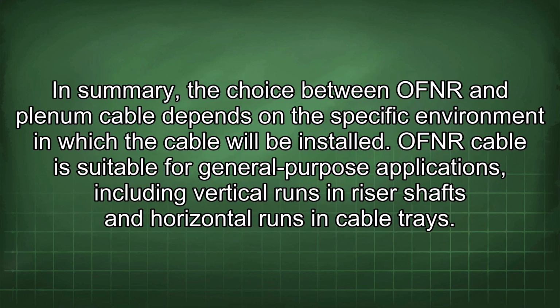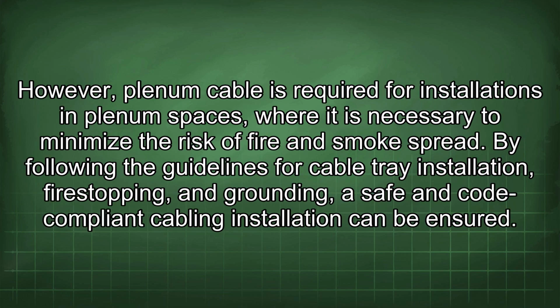In summary, the choice between OFNR and plenum cable depends on the specific environment in which the cable will be installed. OFNR cable is suitable for general-purpose applications, including vertical runs in riser shafts and horizontal runs in cable trays. However, plenum cable is required for installations in plenum spaces where it is necessary to minimize the risk of fire and smoke spread. By following the guidelines for cable tray installation, fire stopping, and grounding, a safe and code-compliant cabling installation can be ensured.